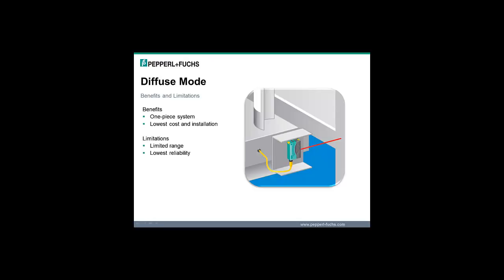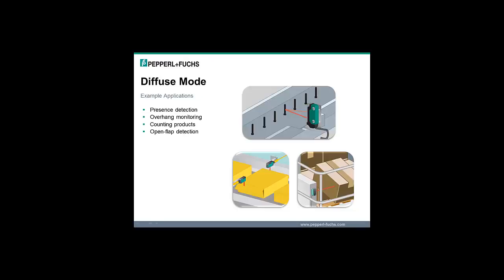Benefits of a diffuse sensor are that it is a one-piece system and does not require a reflector or a through-beam emitter-receiver pair, and it has the lowest cost and installation effort compared to other sensing modes. Limitations are that the sensing range is limited and highly dependent on the characteristics of the object to be detected, and diffuse sensors have the lowest reliability compared to other sensing modes. Example applications include cost-effective presence detection, material overhang detection, presence detection of passing totes or cartons, counting products for palletizing, and detecting open flaps on packaged cartons.